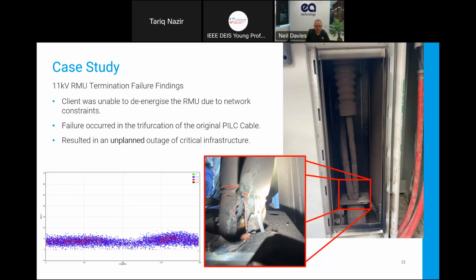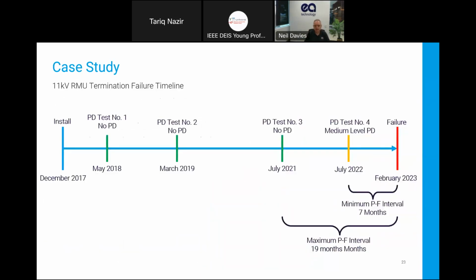So let's think about that on the timeline on our testing type intervals. The ring main unit was installed in 2017. We tested in 18, 19, didn't in 20. There was something else going on around that time. In 21 we did, and then in July 22 we found that level of discharge. So the discharge was not there in July 21, but it was in 22.